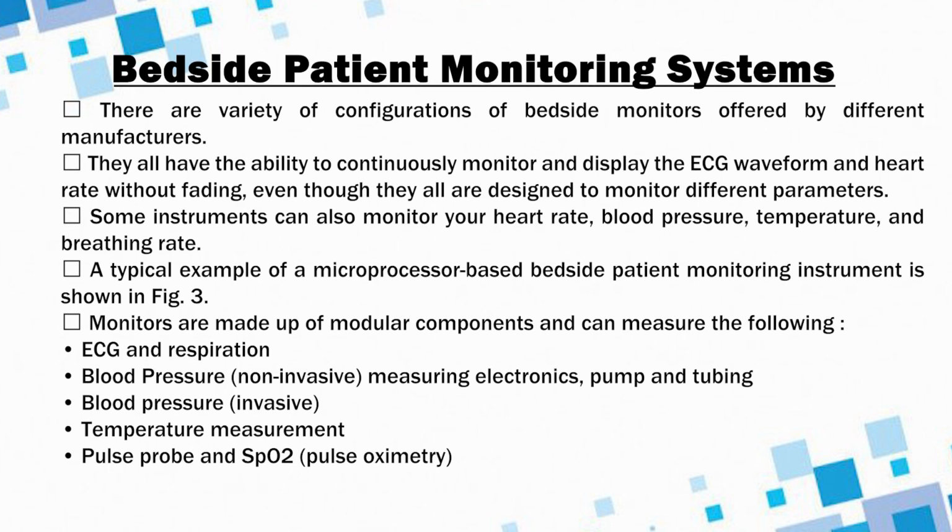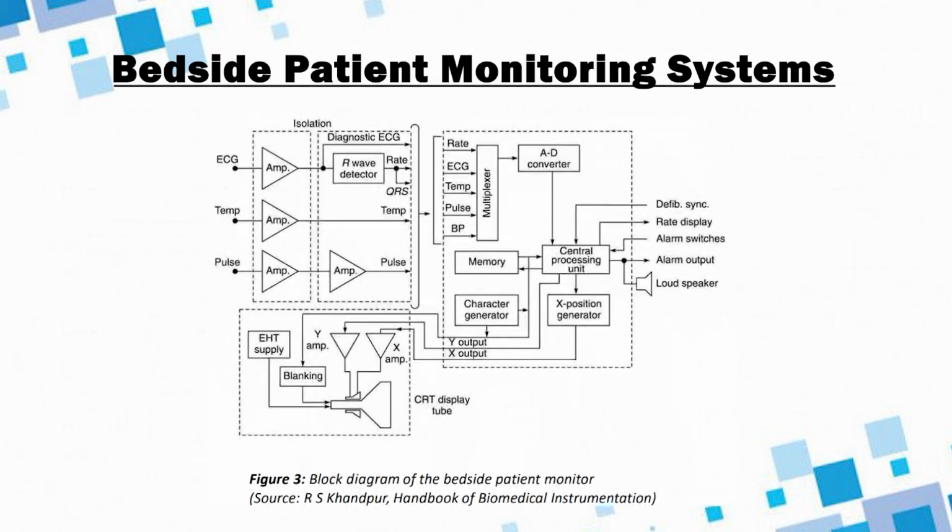Monitors are made up of modular components and can measure the following parameters: ECG and respiration, non-invasive blood pressure (NIBP) measuring electronics, pump and tubing, invasive blood pressure, temperature measurement, pulse probe and SpO2 by pulse oximetry.